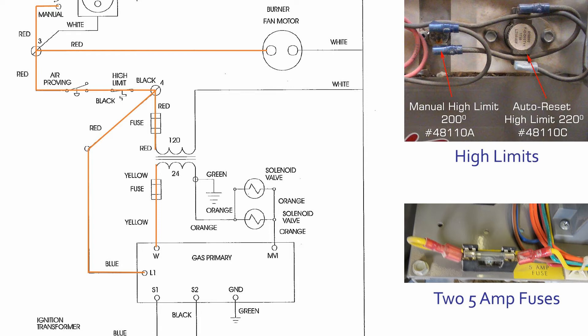At that point, electricity will then move through two 5 amp fuses and energize the primary gas control. The 5 amp fuses protect the primary gas control circuit board.